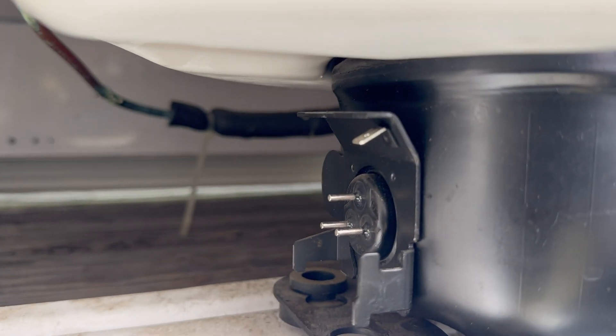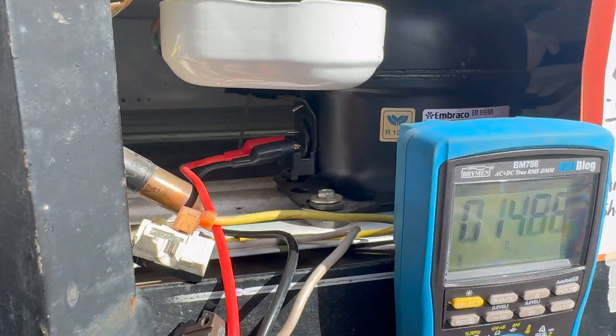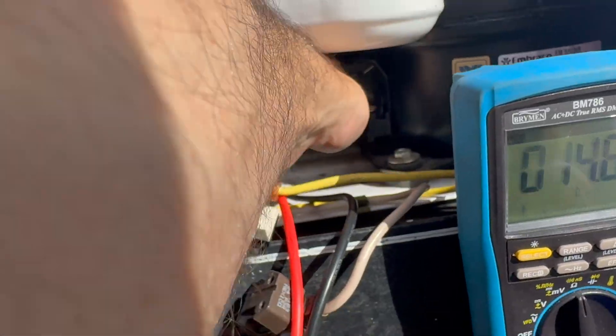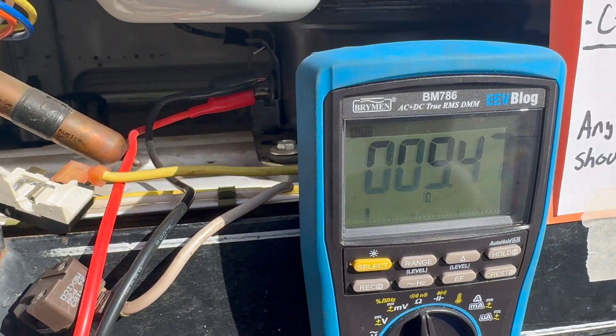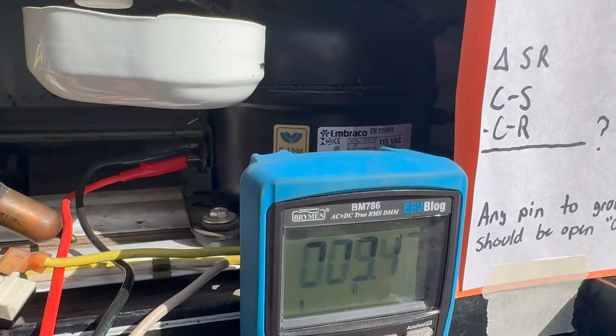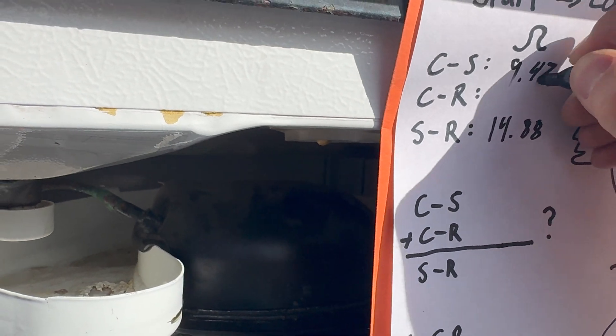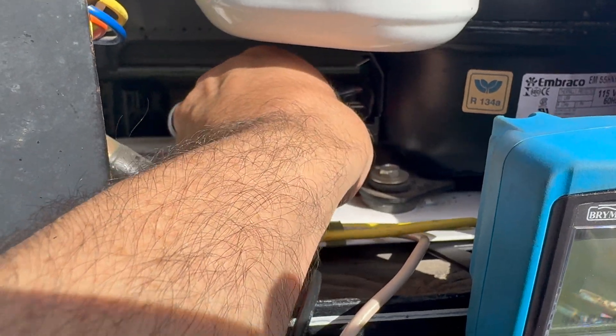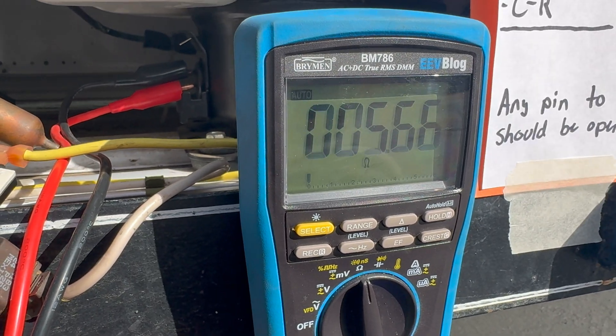I'm connected to the two bottom pins — what I think are start and run — and I measure 14.86 ohms. Next, bottom left to the top center gives 9.47 — I think that's start to common. And lastly, center tap to the right side pin measures 5.67.